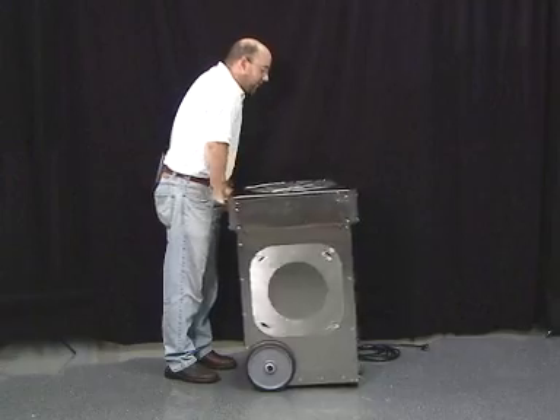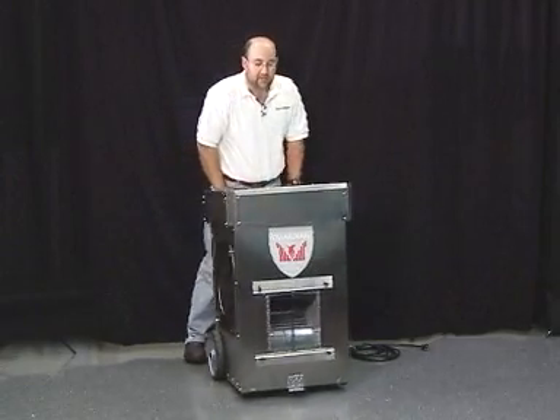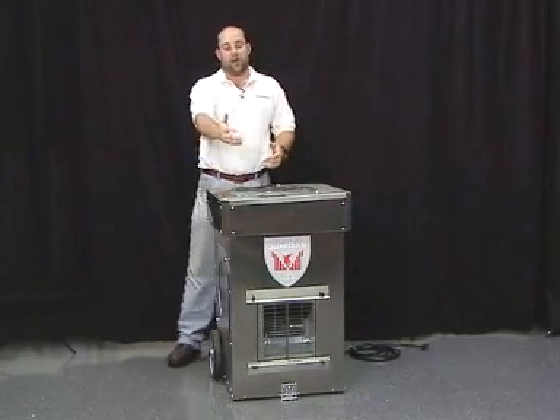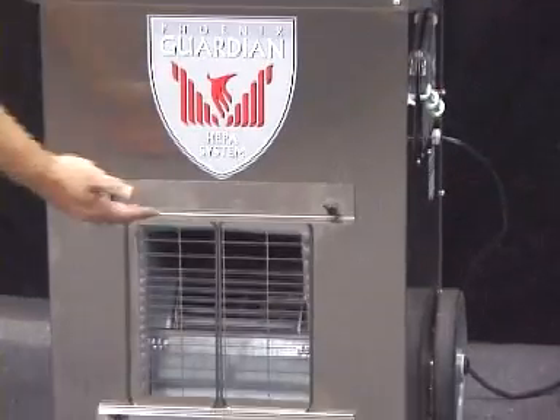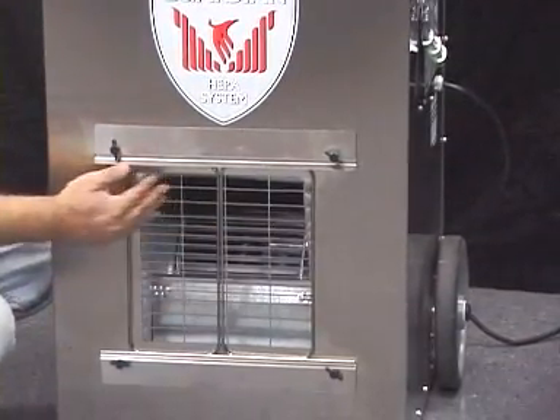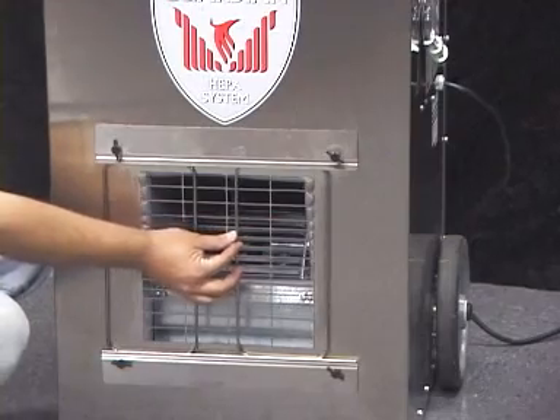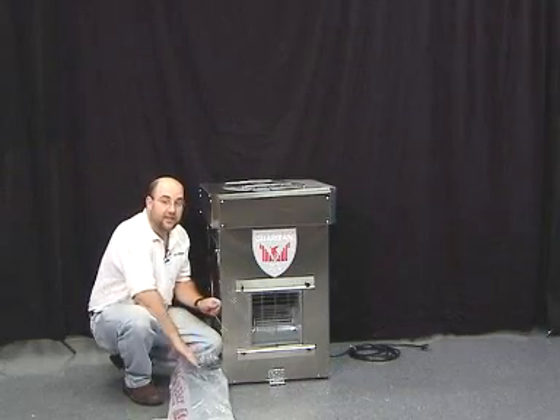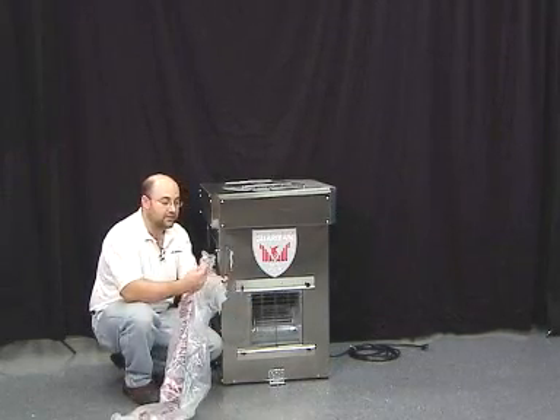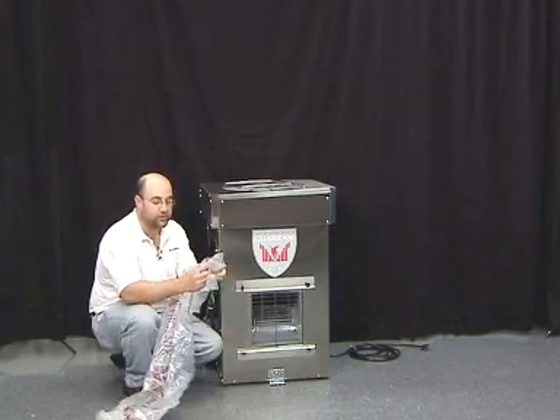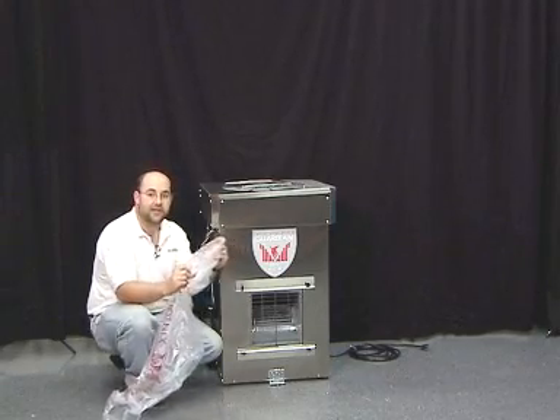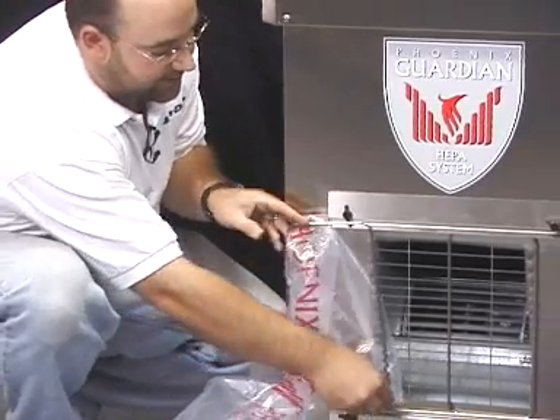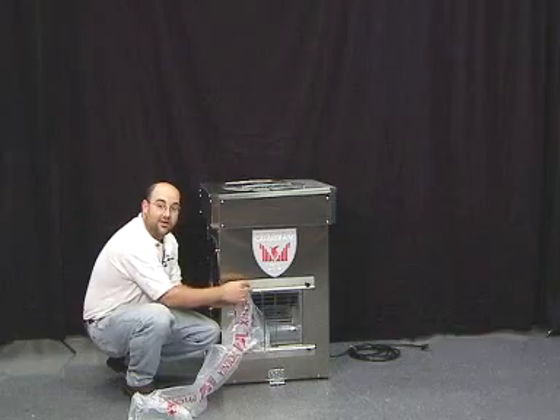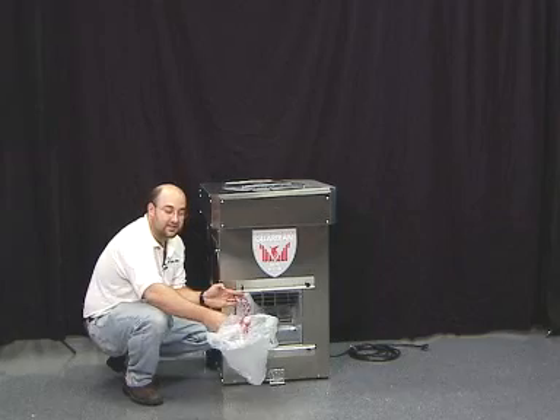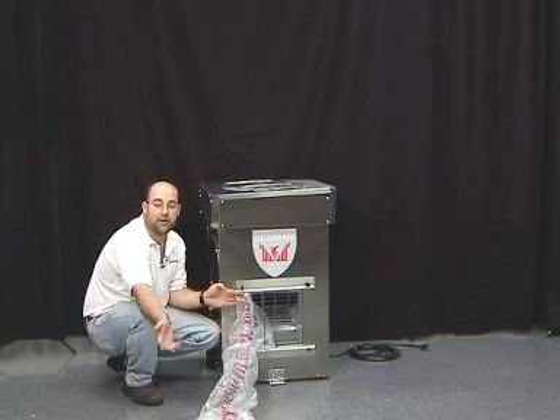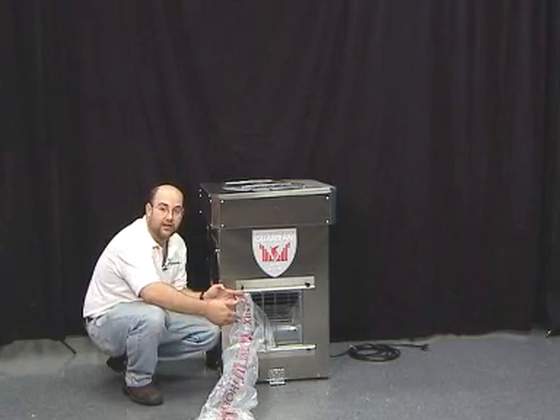If we work our way back around to the front of the machine, that is where the airflow is exhausted off the unit. On the bottom, if I want to attach ductwork, I have a couple different options with this unit. I have the 2 rings. I can pull the ring off, take a standard piece of lay flat, place it through the middle of the ring, then drape it back over the ring. Once I have that secure, I can slide it back onto the track and fasten it down to make sure it's secure. I can then run this ducting out to a window or to another area in the event I need to create a negative pressure.